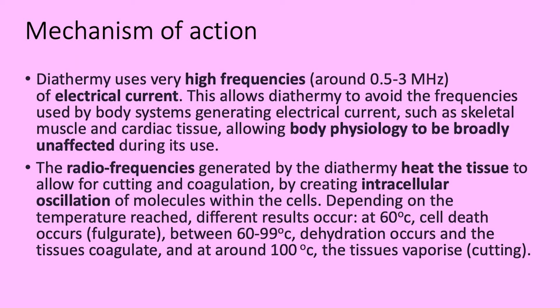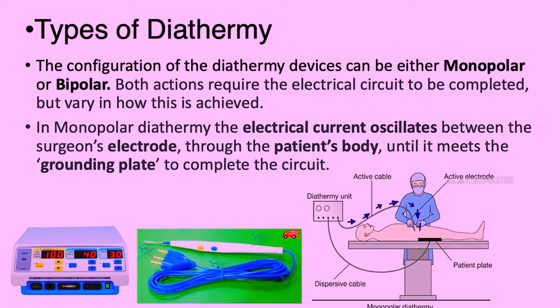This is achieved by creating intracellular oscillation of molecules within the cells. Depending on the temperature reached, different results occur. At 60 degrees Celsius, cell death occurs — that is desiccation. Between 60 to 99 degrees Celsius, dehydration occurs and the tissues coagulate. Around 100 degrees Celsius, the tissues vaporize — that is the cutting effect.